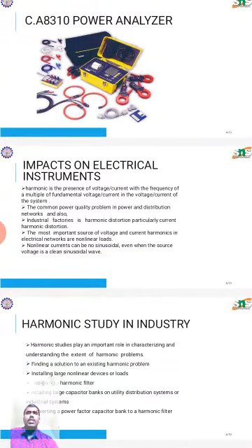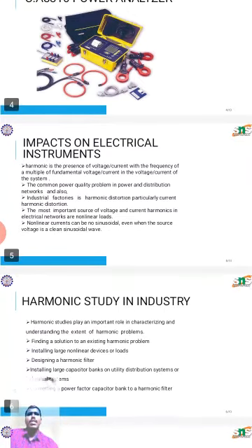Next one, impacts on electrical instruments. The harmonic definition and its impacts on electrical instruments is defined as a sinusoidal component of a periodic wave or quantity having a frequency that is an integral multiple of the fundamental frequency. Therefore, harmonic is the presence of voltage or current with a frequency that is a multiple of the fundamental voltage or current in the voltage or current of the system.